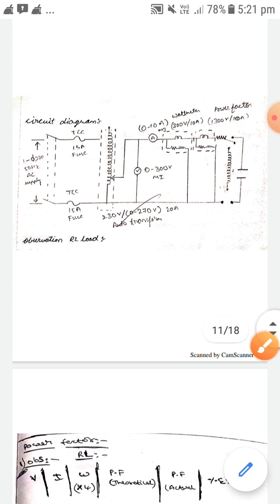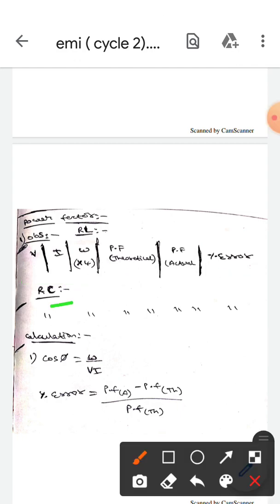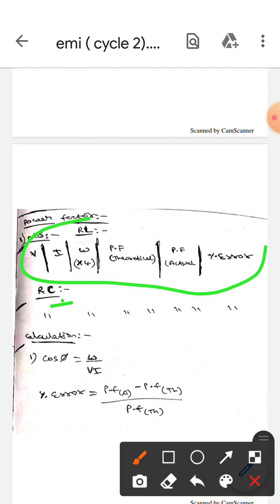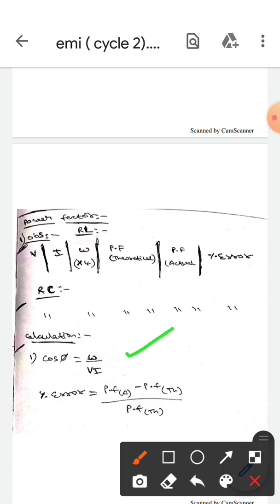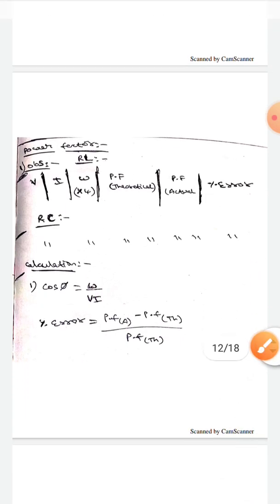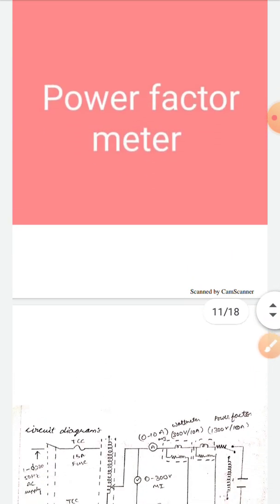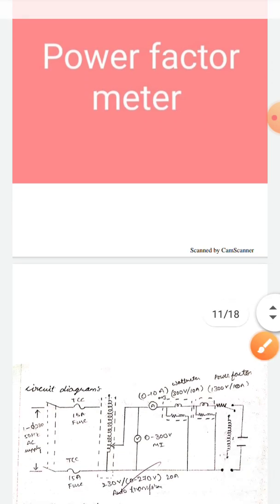This is all about the calibration of the power factor meter. In table form we write: V, I, W, PF theoretical, PF actual, and percentage error — the same table is used for the RC load as well. The formula used is cos φ = W / VI, and percentage error = (PF actual − PF theoretical) / PF theoretical. This is all about the calibration of the dynamometer-type power factor meter. I hope you understood, guys. Thank you.